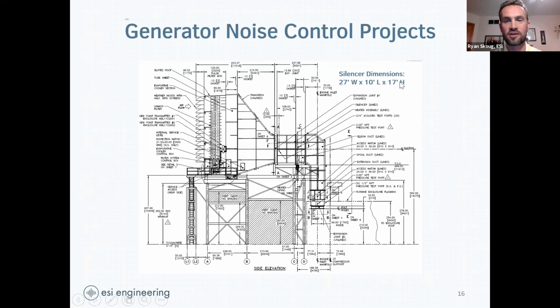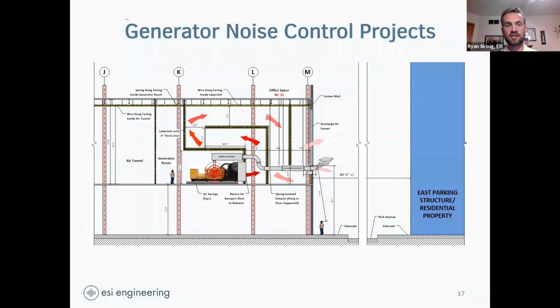It was really fun to engineer these silencers to perform right, changing the baffles. A silencer is a big box with baffles, air can get through them, but it attenuates the noise as it goes through this 10-foot length. We engineered what the baffle dimensions had to be and how many to put in the bank of silencers to provide the sound insertion loss we needed. Those are always really interesting.